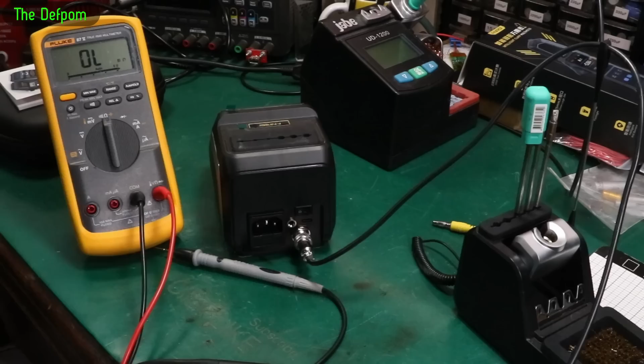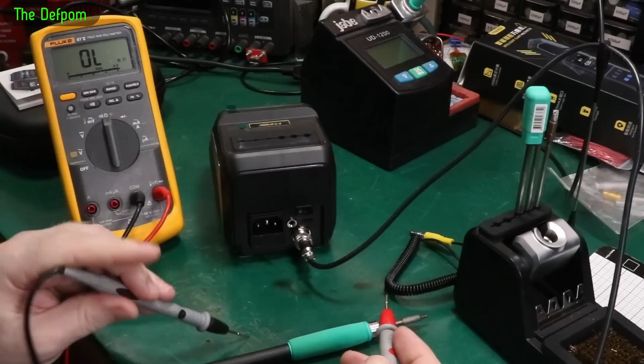You can see I'm prepared here, soldering iron tip plugged in. I've unplugged the lead which runs to the base, which is normally used for the sensing, so it goes into the casing here. Between the lead and there, there's like 0 ohms, okay, or 1 ohm. So that plugs into this. You'd think normally that would be an earth.